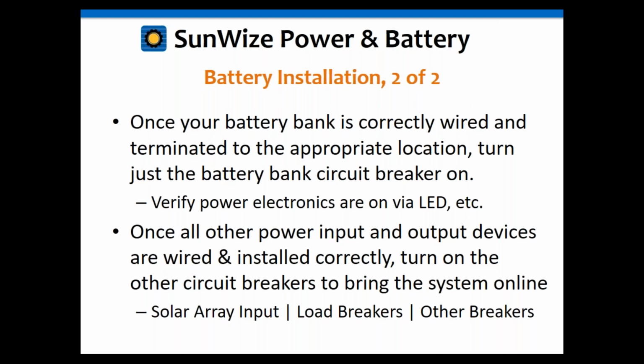So you're going to turn that on, and use a multimeter to perhaps verify voltages and polarities. Check the power electronics and make sure the LEDs are on and everything is good, whether it be powering an inverter directly or powering up a charge controller, just want to check and verify those things have come on and have proper status before proceeding. Once that's done and everything looks good, then you can proceed with turning on the other devices, like load breakers, solar array inputs, and things like that.